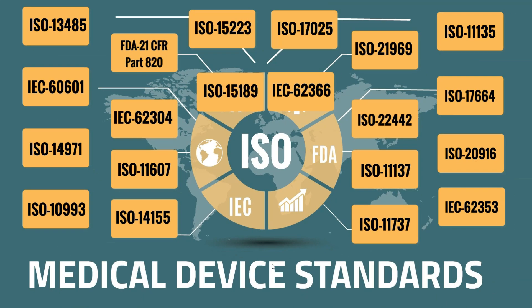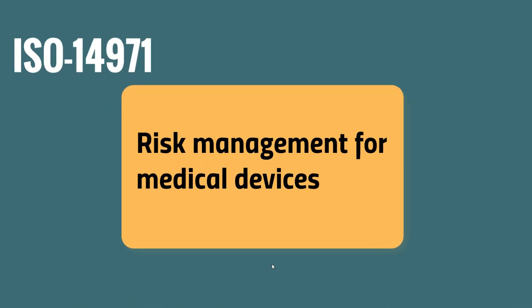3. ISO 14971 — this is the ISO standard for risk management for medical devices. This standard outlines a process to identify the hazards associated with medical devices, and helps ensure the safety of a medical device during the product life cycle.